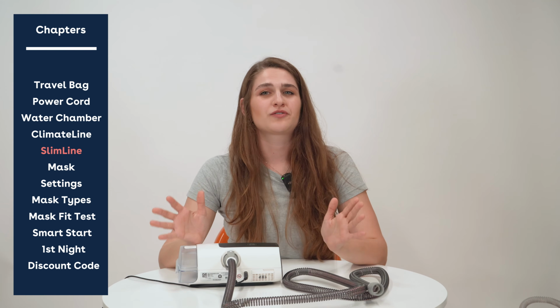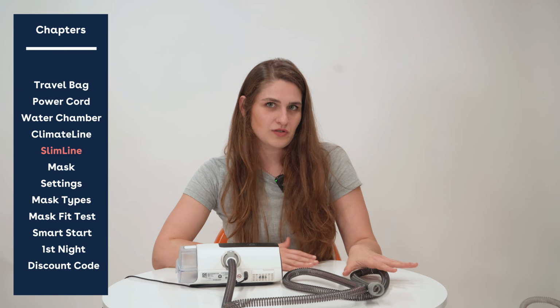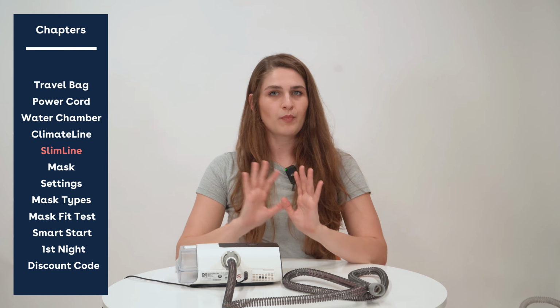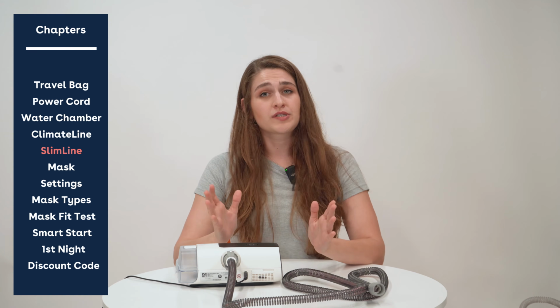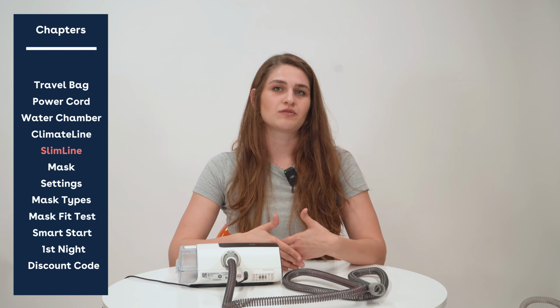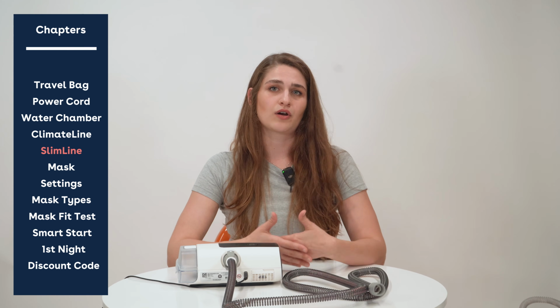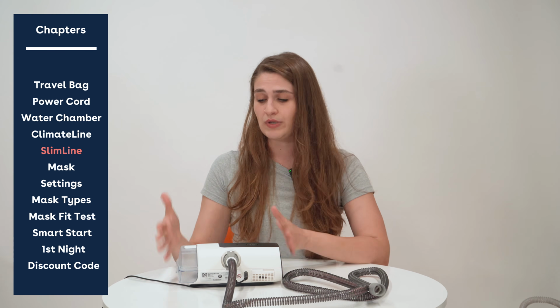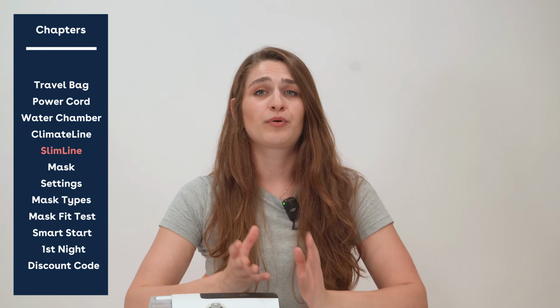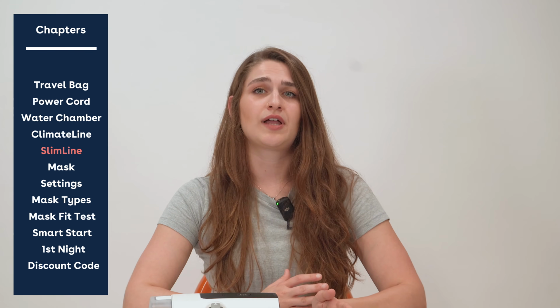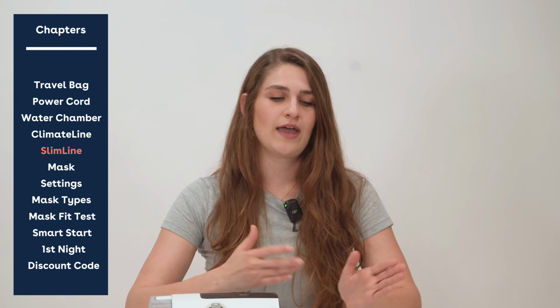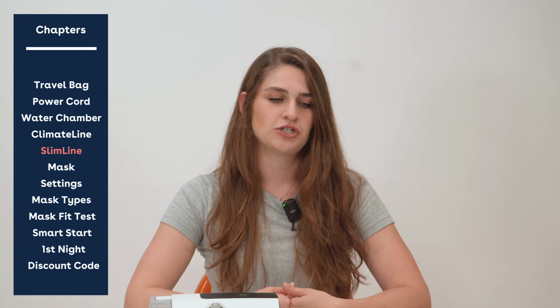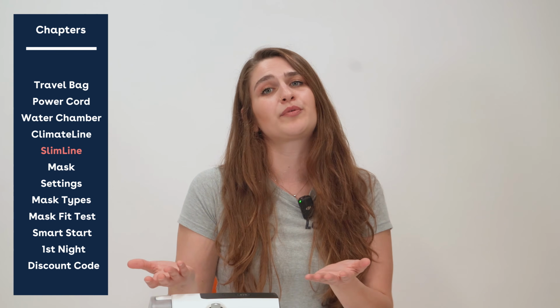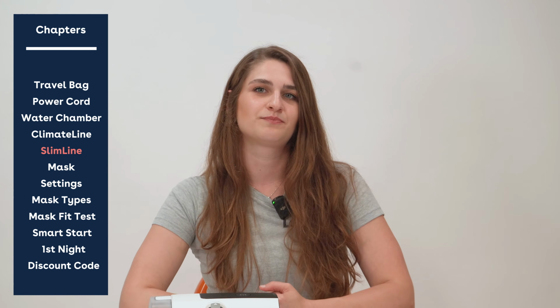Now you might be wondering, why would you even want the heated tubing option? So honestly, it won't affect the performance of your device, but it will assist with issues like rain out or water buildup that can occur in your mask or tubing when the humidity is a little too high. Now, if you purchase the SlimLine and you want to switch over to ClimateLine, it's not a problem. Every 6 months or so, we do recommend changing out your tubing, so it would be a good opportunity to switch it out when it's needed.